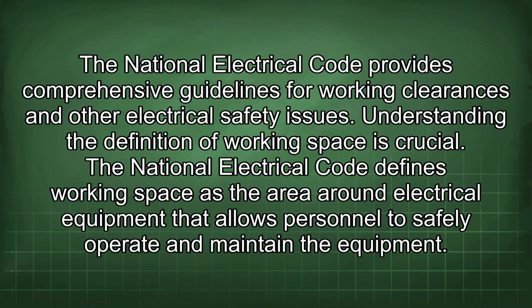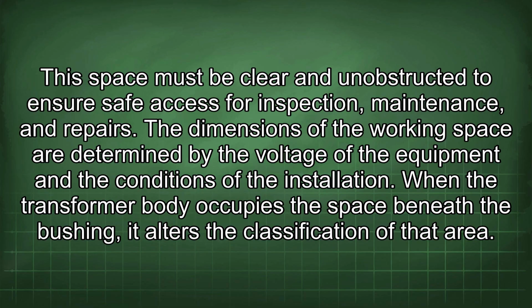Understanding the definition of working space is crucial. The National Electrical Code defines working space as the area around electrical equipment that allows personnel to safely operate and maintain the equipment. This space must be clear and unobstructed to ensure safe access for inspection, maintenance, and repairs. The dimensions of the working space are determined by the voltage of the equipment and the conditions of the installation.